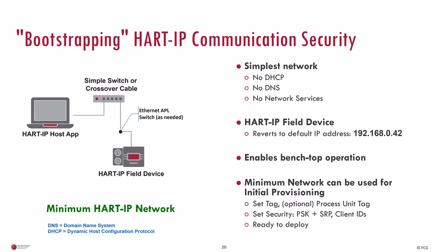One of the tricky things about communication security is how do you get started? What is that first step? We designed HART-IP so that you could work on an air-gapped network with just a device and just a client. It means nobody can see what you're doing or look at the credentials that you're entering. In this case, the HART-IP field device is going to default to 192.168.0.42. That way you can connect to it.